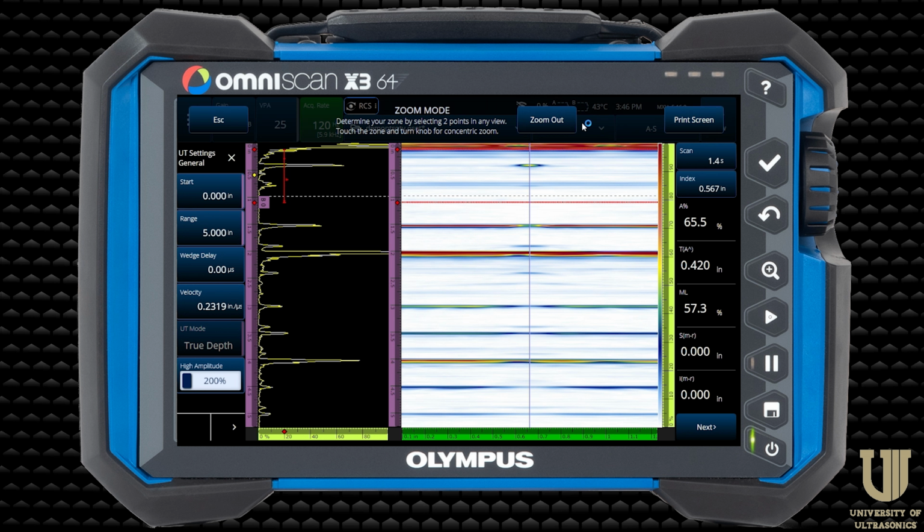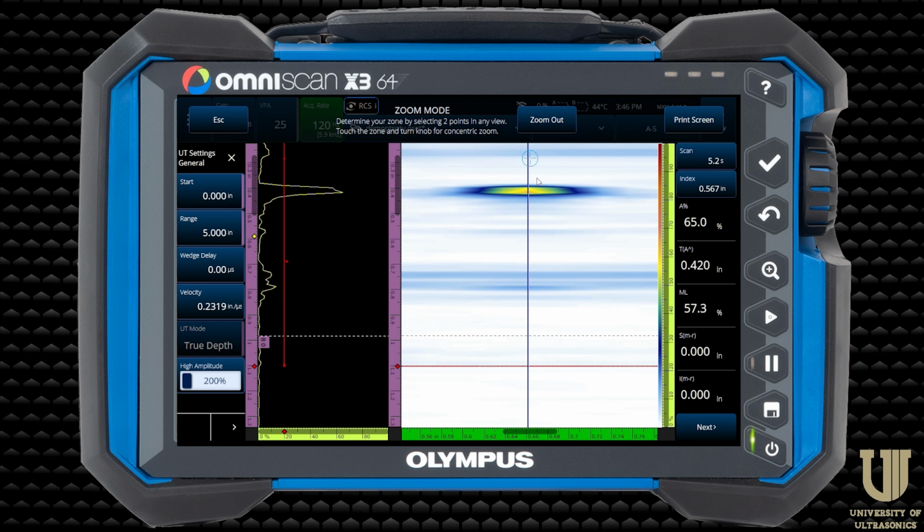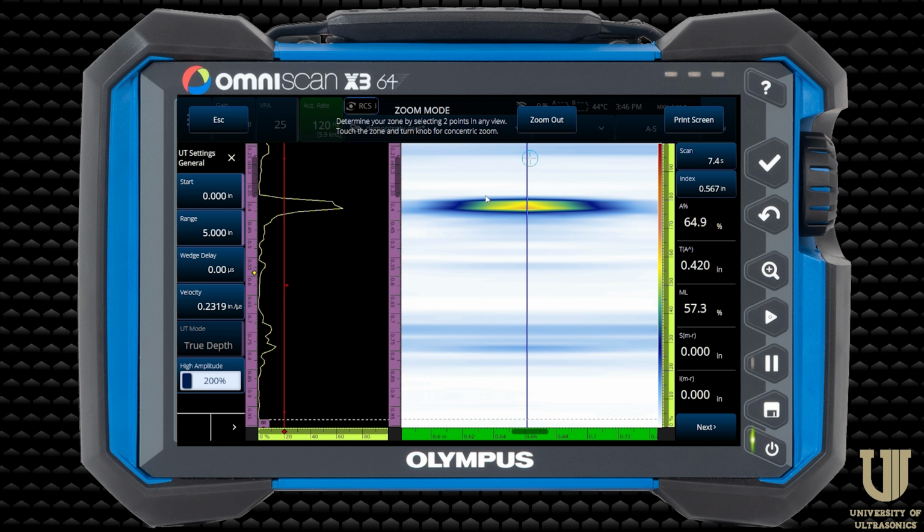I'm mainly worried about our little side drilled hole signal up there, right? So at a 5-inch range, the resolution has gotten even worse because again, those same 568 points spread out over that bigger range, I have more compression and now a lower net digitization frequency.